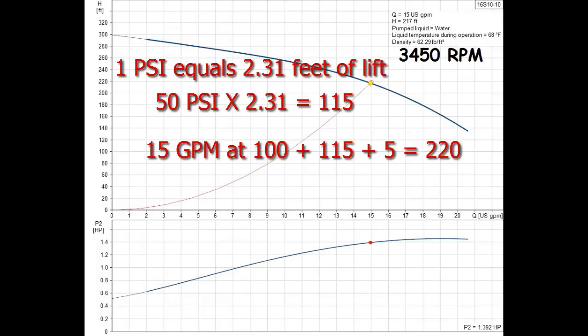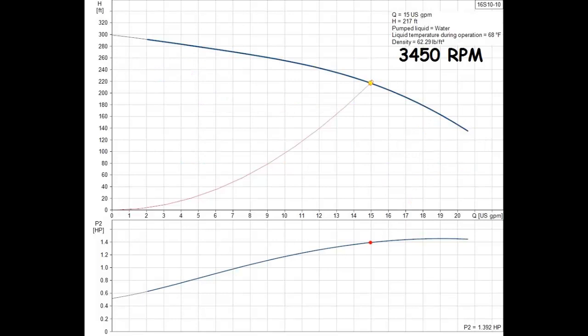That 115 feet of lift for the pressure must be added to the actual pumping depth to water in the well. If the pumping water level in the well is 100 feet and there is 5 feet of friction losses in the pipe, the pump must be able to produce 15 gallons per minute from 100 foot depth plus 115 feet which is the 50 pounds pressure needed plus 5 foot of friction loss for a total dynamic head of 220 feet.